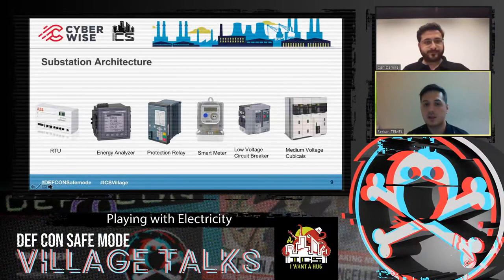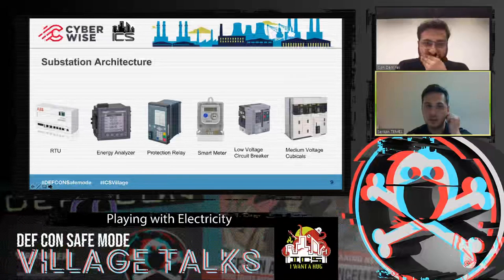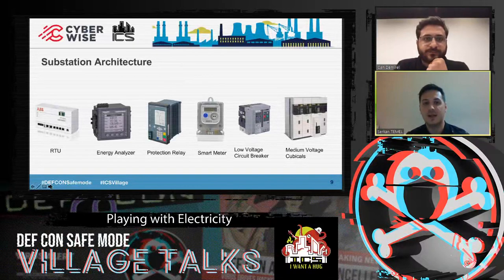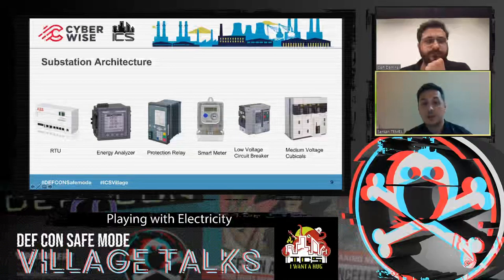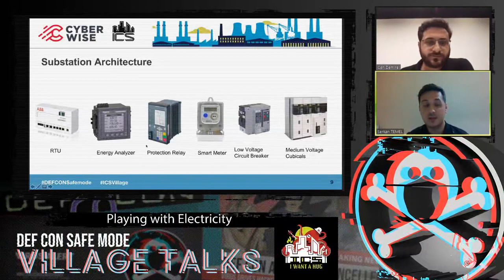Energy analyzer is an energy meter which gets information from the CT and VT transformers, from electric site information, translates it into the digital side, and directly sends this information to SCADA systems. Protection relay is a critical equipment in the distribution and also transmission and also generation, as you know. Protection relay is the first IED device, the first electronic device connected to the physical electric system. It is a bridge between the cyber and physical world.